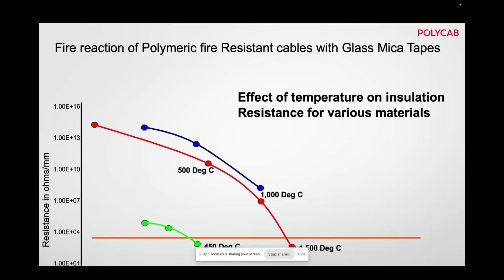Here is the Polycab Ignis brand fire survival cable. We have the Ignis brand fire survival cable with a number designated as 200, 201, 202, 203, like this, because that depends on whether it is a power cable, a control cable, a communication cable or an instrumentation cable. That defines it. So this cable maintains circuit integrity up to 3 hours at 950-degree temperature.